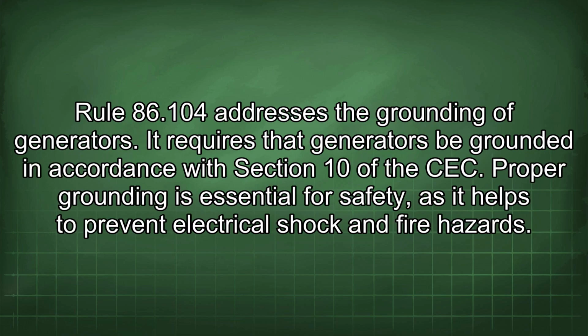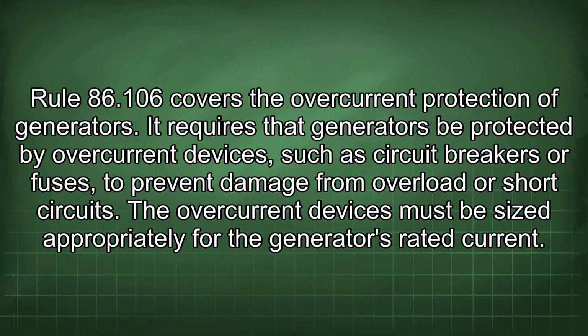Rule 86.104 addresses the grounding of generators. It requires that generators be grounded in accordance with Section 10 of the CEC. Proper grounding is essential for safety, as it helps to prevent electrical shock and fire hazards. Rule 86.106 covers the overcurrent protection of generators. It requires that generators be protected by overcurrent devices, such as circuit breakers or fuses, to prevent damage from overload or short circuits. The overcurrent devices must be sized appropriately for the generator's rated current.